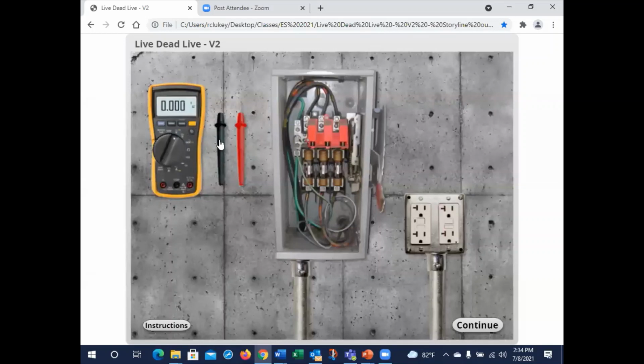But in this case, we're going to use this receptacle to go ahead and test our meter on a known voltage. I like putting the common lead where our neutral conductor would be on that receptacle. And then I bring over my volt/ohm lead and put it on the energized conductor. And we can see this receptacle is working just fine. So, which means my meter is working perfect. So I know the voltage on a receptacle is going to be 120 volts. My meter tells me 120 volts. So I've done the first step very well. I have determined that my meter is working properly.